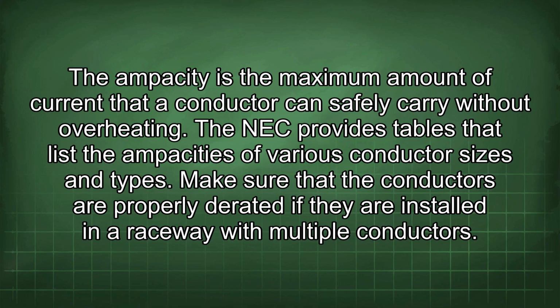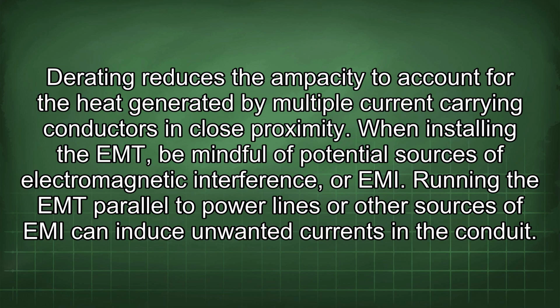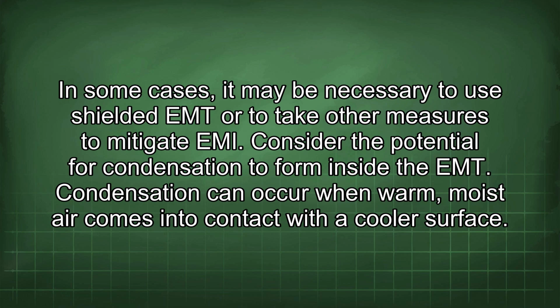Make sure that the conductors are properly derated if they are installed in a raceway with multiple conductors. Derating reduces the ampacity to account for the heat generated by multiple current-carrying conductors in close proximity. When installing the EMT, be mindful of potential sources of electromagnetic interference, or EMI. Running the EMT parallel to power lines or other sources of EMI can induce unwanted currents in the conduit. In some cases, it may be necessary to use shielded EMT or to take other measures to mitigate EMI.